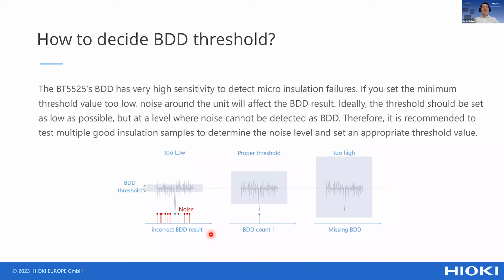But the most tricky part is how to determine whether there was a BDD happening. So how is this being done? We have seen you have 3 areas you can set as a threshold, and once you have outliers, these will then be counted as a BDD. But the most tricky part is how to set these thresholds correctly. So one of the main features is that we have a higher noise resistivity. And this is very, very important when you want to set thresholds as close as possible. In a production environment, you have much noise around, coming from conveyor belts, so everything where you have frequencies and frequency inverters, in robotics, pick and place. And therefore, the higher noise resistivity is very, very important to make the BDD count as accurate as possible.